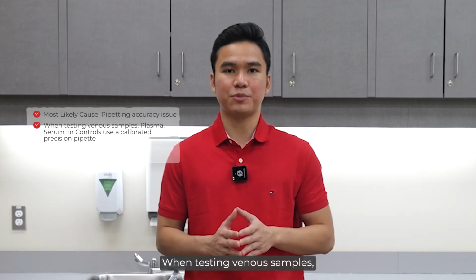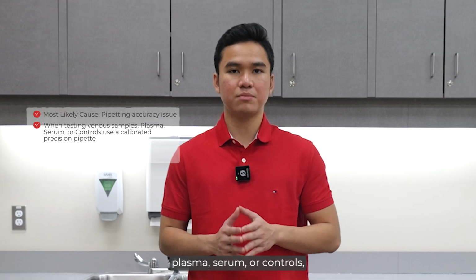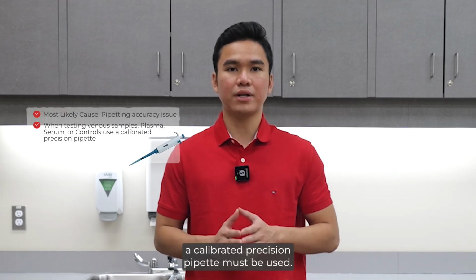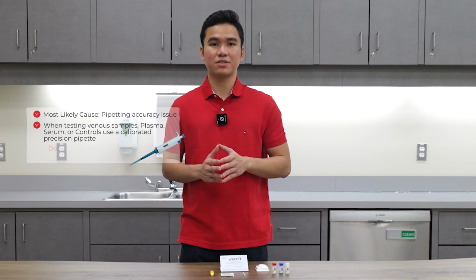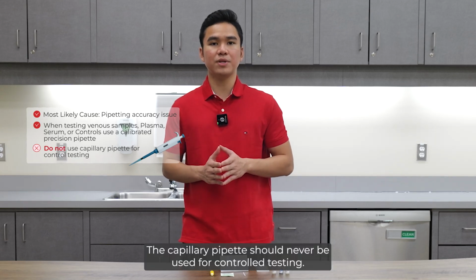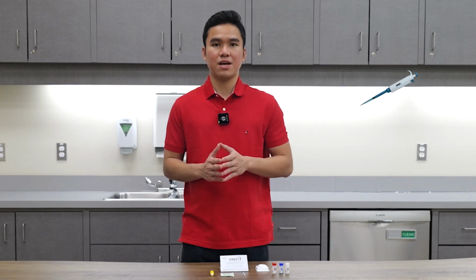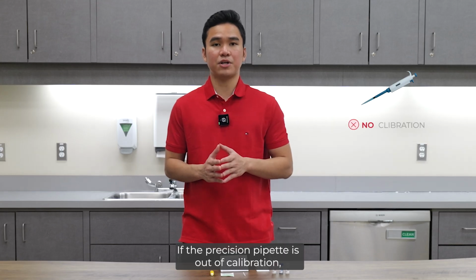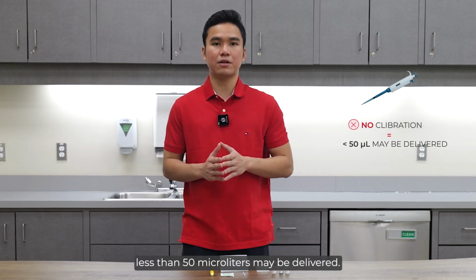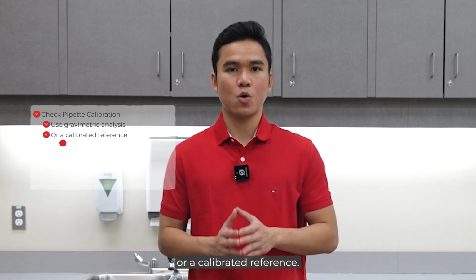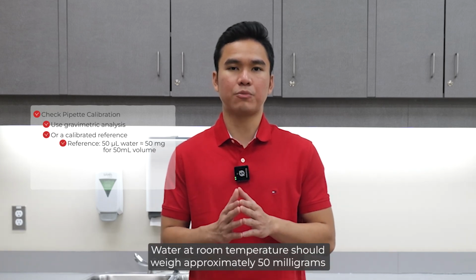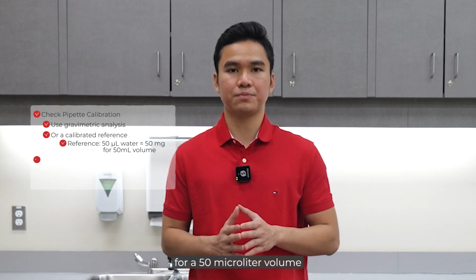When testing venous samples, plasma, serum, or controls, a calibrated precision pipette must be used. The capillary pipette should never be used for control testing. If the precision pipette is out of calibration, less than 50 microliters may be delivered. Check pipette calibration using gravimetric analysis or a calibrated reference. Water at room temperature should weigh approximately 50 milligrams for a 50 microliter volume.